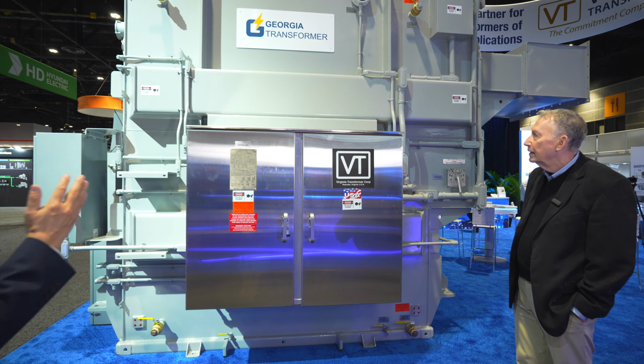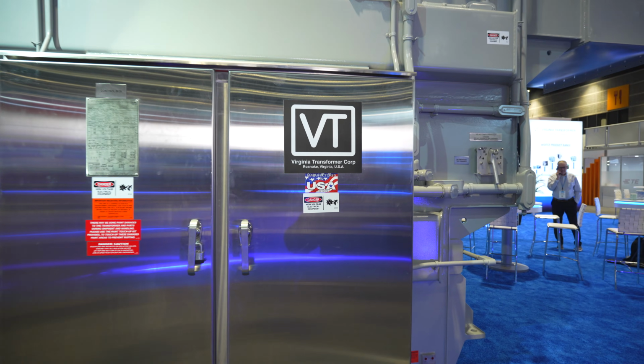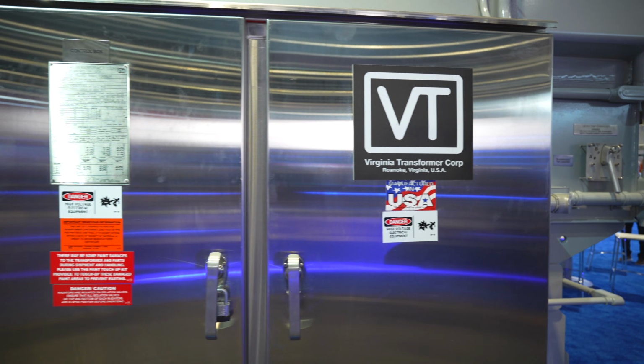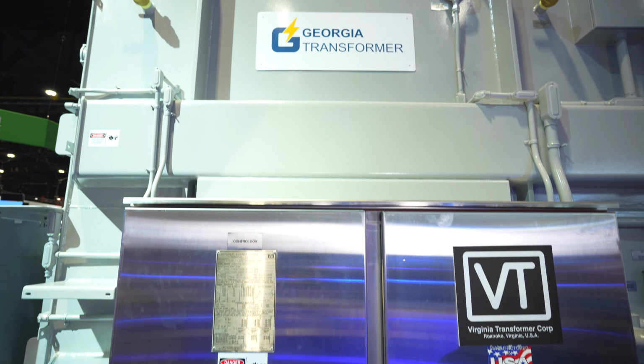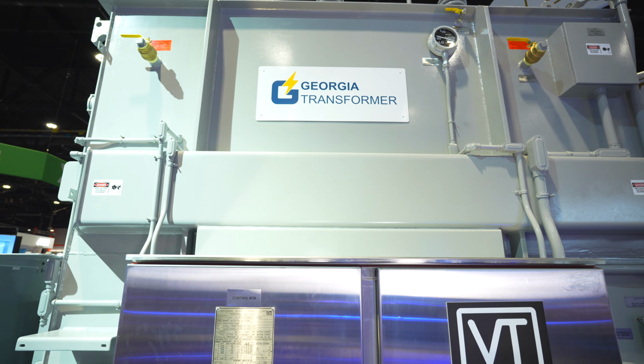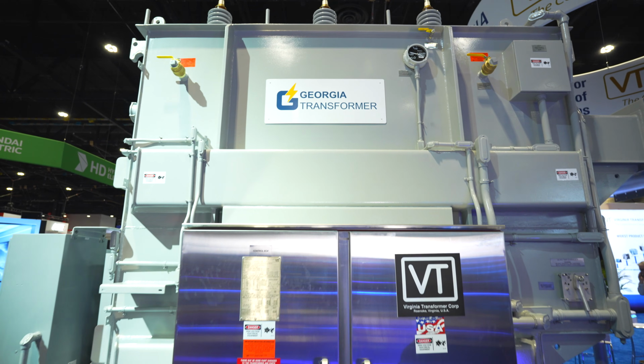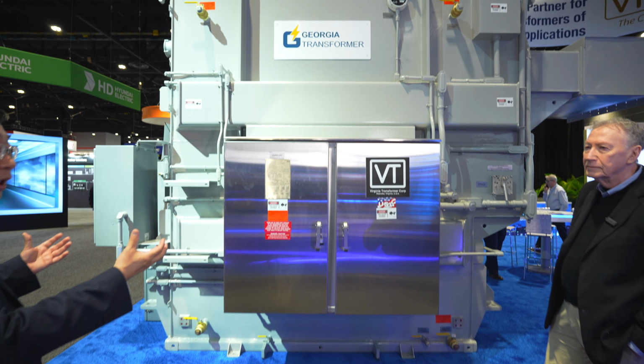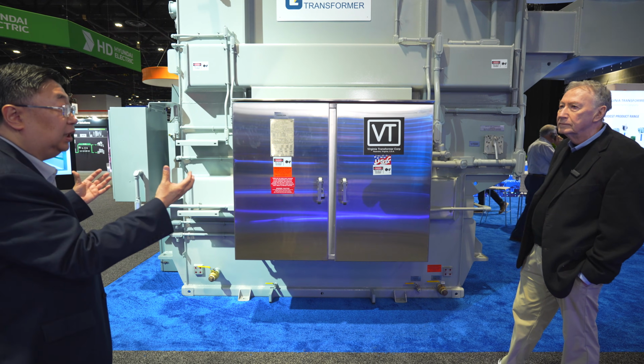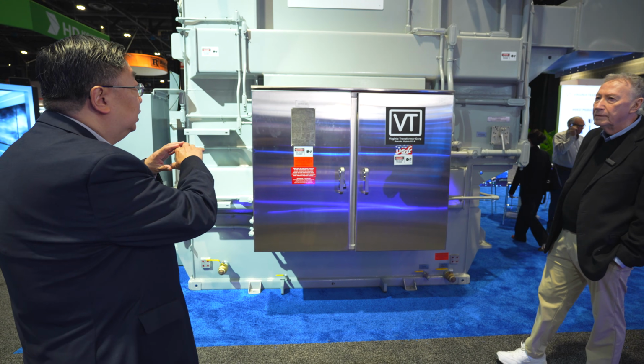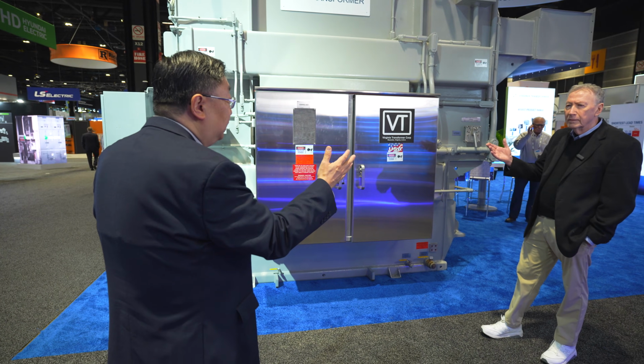This particular unit has a base rating of 15 MVA. With the fan kicking in, it can go up to about 25 MVA. This is a very typical design that a U.S. utility would order—it's like a backbone of a lot of our U.S. infrastructure, in the 10 to 30 MVA transformer range.